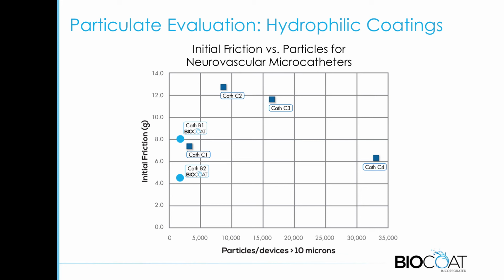Putting this all together, you can look at both the friction and the particulate generation on the same graph, and it really differentiates between the various coatings. Some have low particulates but higher friction. Others have lower friction but higher particulates. That has traditionally been a trade-off between the two. Now, with the best-in-class ones, you can have both. Lower is better on both, so you can have both low friction and low particulates.